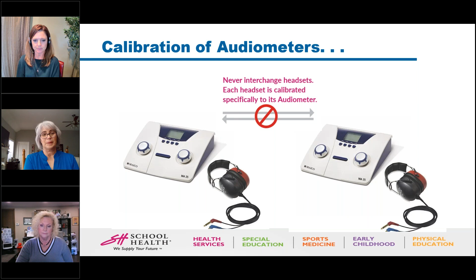So right, not interchanging the headphones. One benefit, you mentioned the Easytone. The Easytone, because the audiometer is actually within the headphone, is a different type of transducer than what we see, but because the calibration is held within the headphone for the Easytone device, that can transfer from one tablet to another. So that's something else to understand, the differences between standard traditional audiometers and the newer products that are being introduced, such as the Easytone.